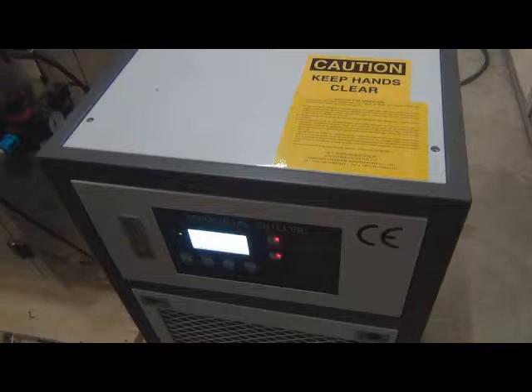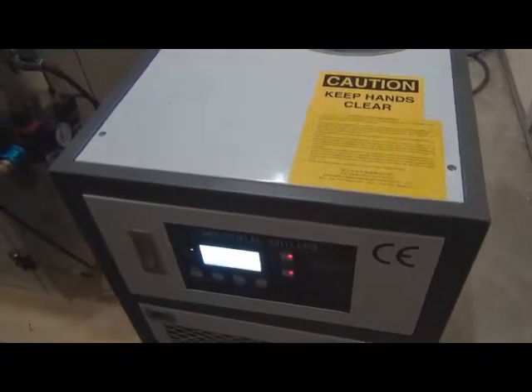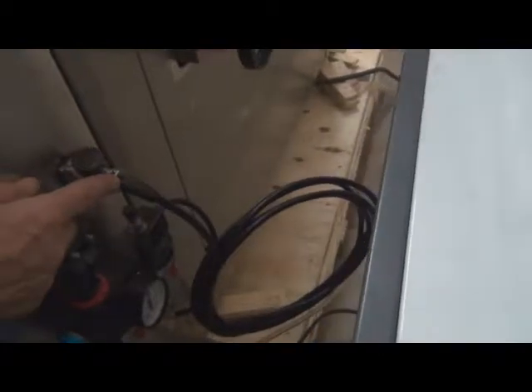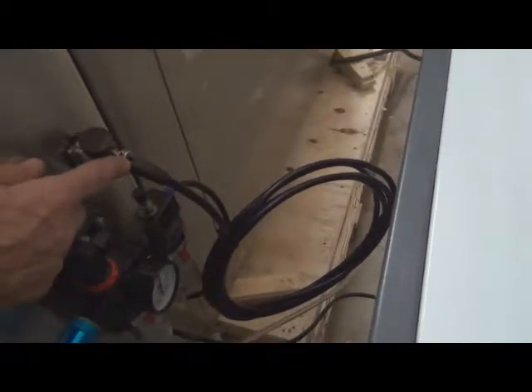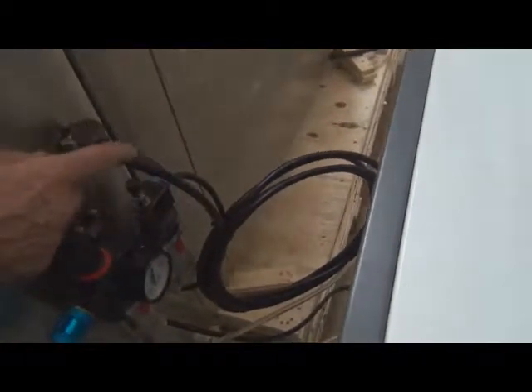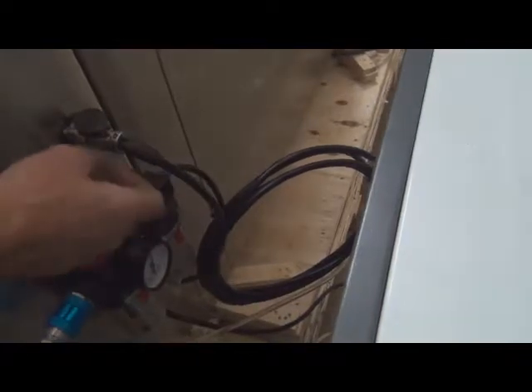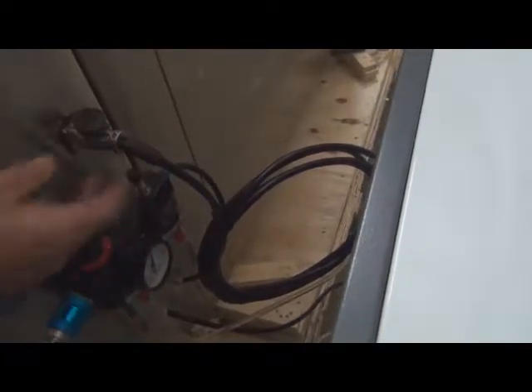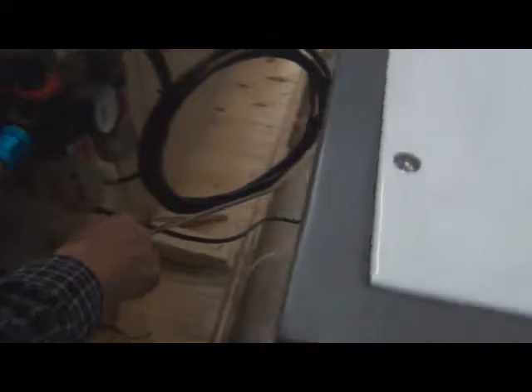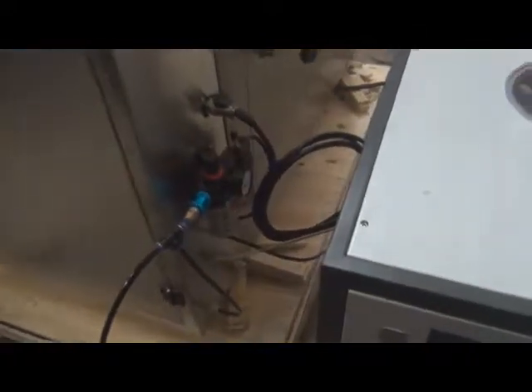The only other thing, really — there's 3 connections. The power to the chiller and the feedback from the thermocouple is here, that's just one plug, and then there's two lines, a clear one and a black one, that connect to the side of the filling unit here.